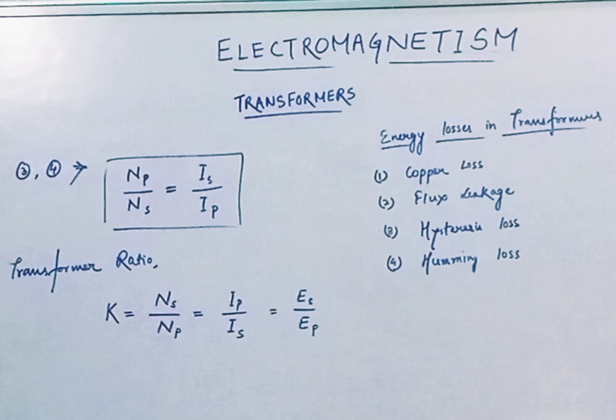Okay, the next is humming loss. Humming is a kind of sound which occurs when the transformer works, because the core is continuously working, right, between the alternating voltage. If it's increasing the voltage or it's decreasing the voltage, it is going through a cycle of work, and because of this it gives rise to a humming sound. Transformer to produces a humming sound, and that is nothing but some kind of electrical energy which is lost in the form of sound energy.